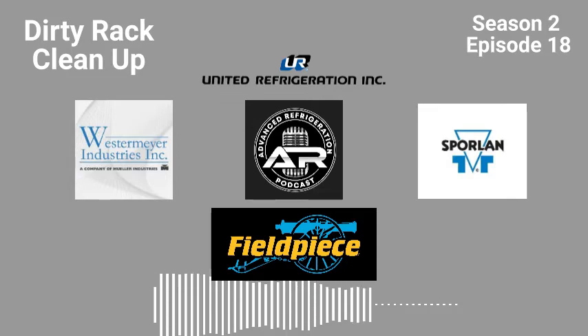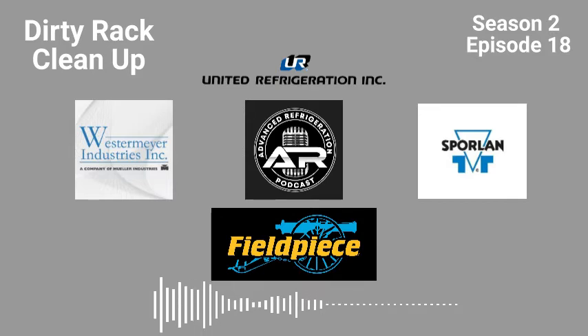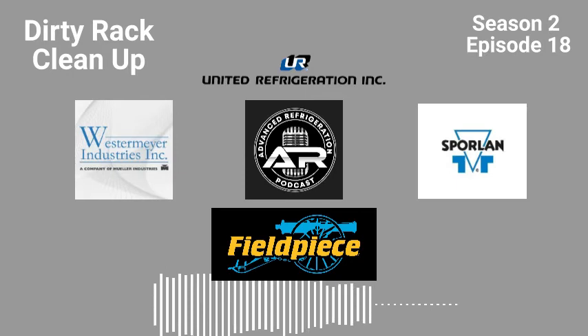The CO2 oil is still POE oil. It's just 85 weight. But yeah, just going through, the biggest thing, you guys, is getting everything cleaned up. I see suction filters all the time that are blown out. We just did case change outs on a bunch of racks, and part of the store's requirement is you have to change all the filters when you're done, no matter what. If it's one case on the rack, you have to change the liquid, the oil, and the suction filters.